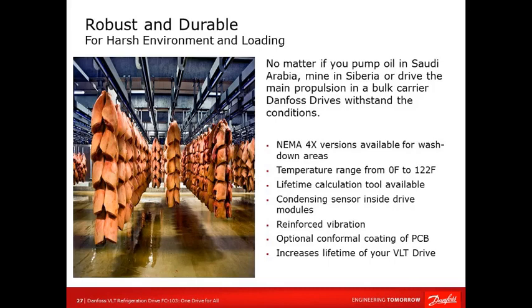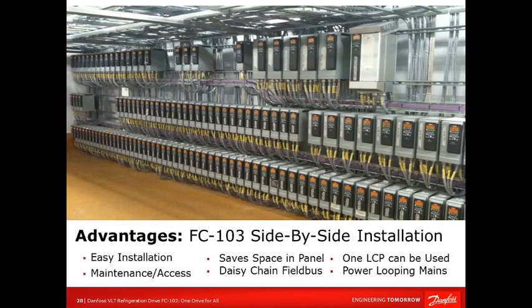What we talk about, conformal coating on the printed circuit board, we're used to from experience working in water wastewater treatment facilities, so a lot of acidic and corrosive environments. Therefore, we coat these circuit boards so that the ambient environment, and what's in the environment, is not going to corrode the electronics of the drive. And again, we want over 10 plus years of life expectancy of the drive. So we try to include a lot of capability into it so that there are no issues. And obviously we can have the drive with its own enclosure, so you're not having to take a drive and put it in another enclosure. We can easily supply standard product in NEMA 12 or NEMA 4X if that's required.